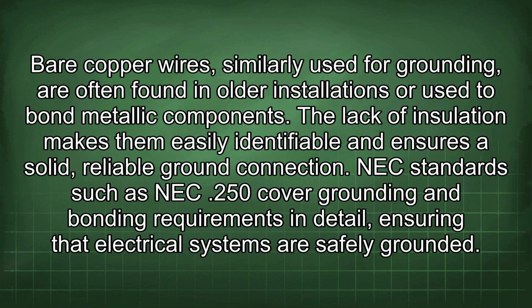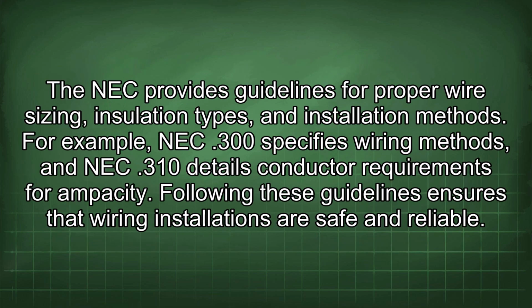Bare copper wires, similarly used for grounding, are often found in older installations or used to bond metallic components. The lack of insulation makes them easily identifiable and ensures a solid, reliable ground connection. NEC standards such as NEC 250 cover grounding and bonding requirements in detail, ensuring that electrical systems are safely grounded. The NEC provides guidelines for proper wire sizing, insulation types, and installation methods. For example, NEC 300 specifies wiring methods, and NEC 310 details conductor requirements for ampacity. Following these guidelines ensures that wiring installations are safe and reliable.